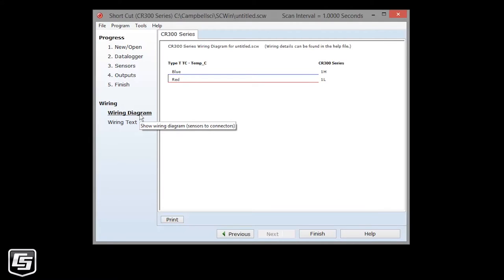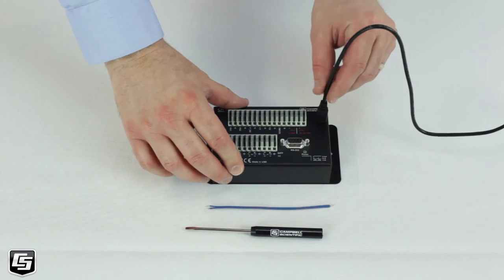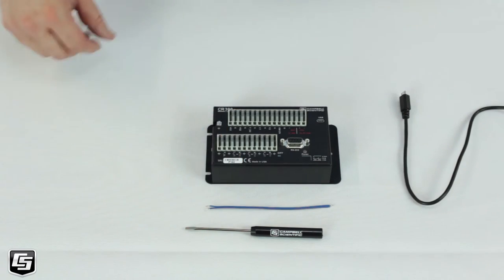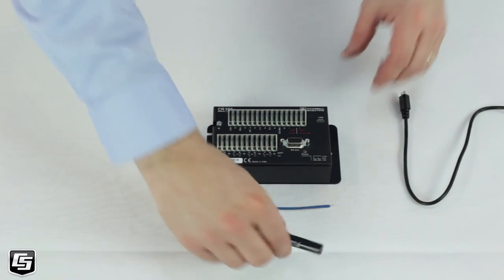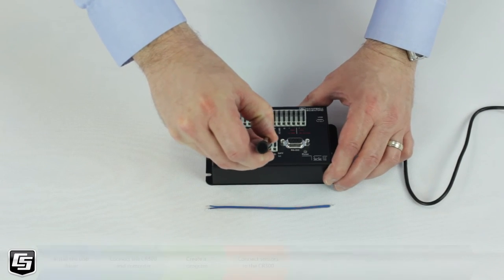The wiring diagram and text provided show where the sensor leads must be connected to the data logger's wiring panel to take good measurements. Incorrect wiring, or not following the diagram provided, is a common new user error. It's good practice to remove power from your data logger before making changes to your wiring. I'll disconnect the USB cable.